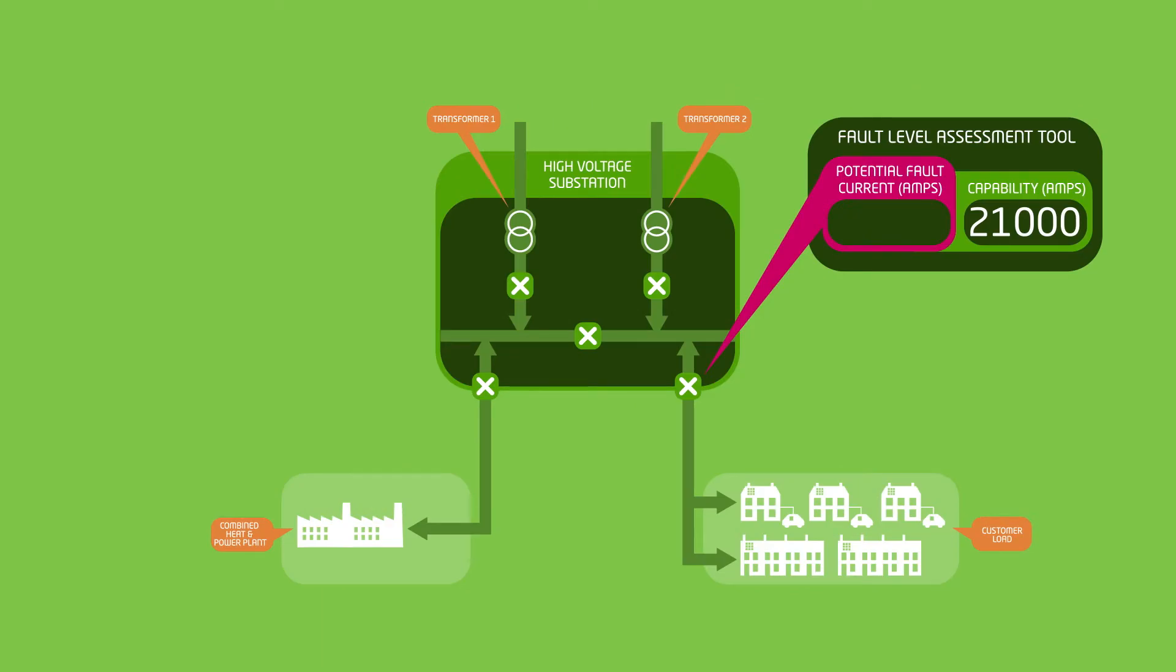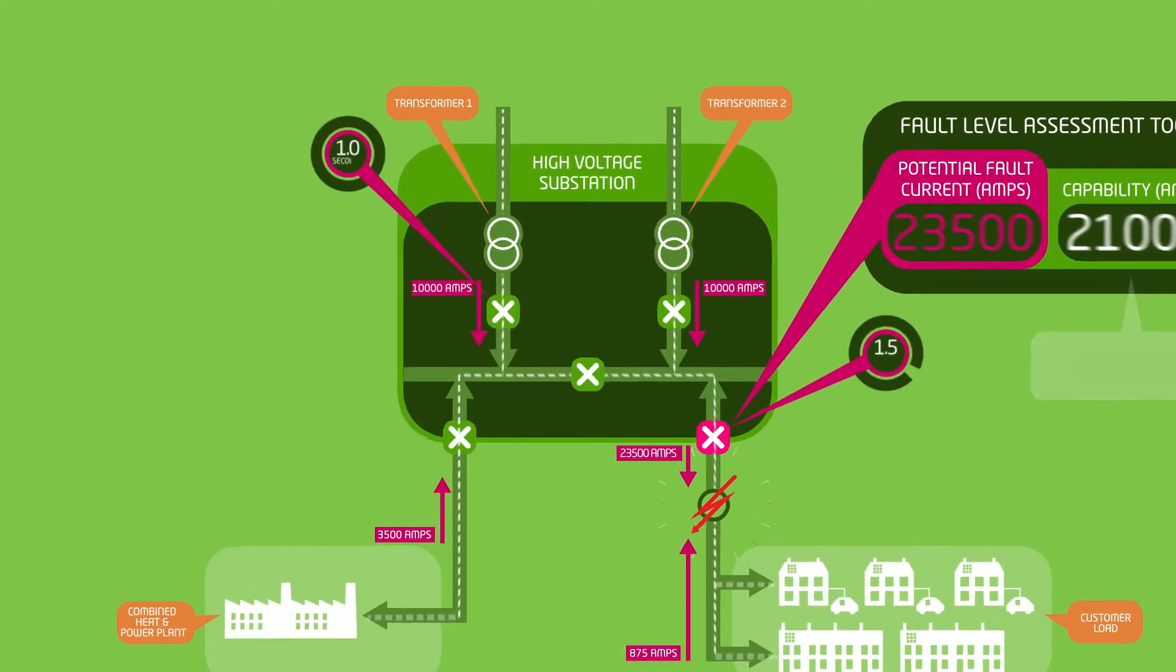Adaptive protection changes the order in which these circuit breakers trip. In this example, the equipment on the network can handle a current of 21,000 amps for three seconds before it might be damaged.